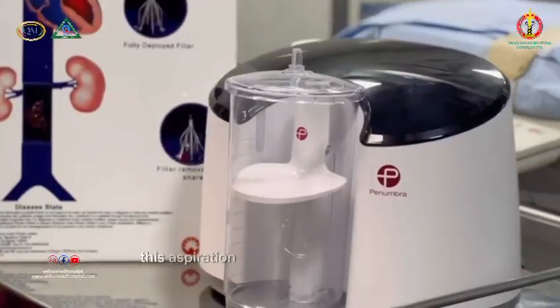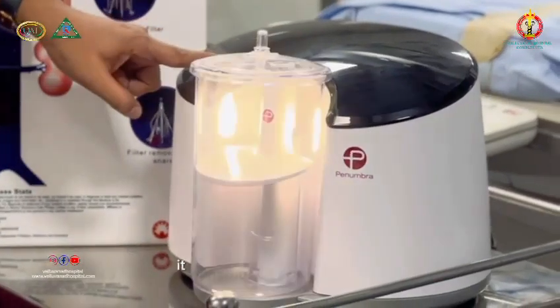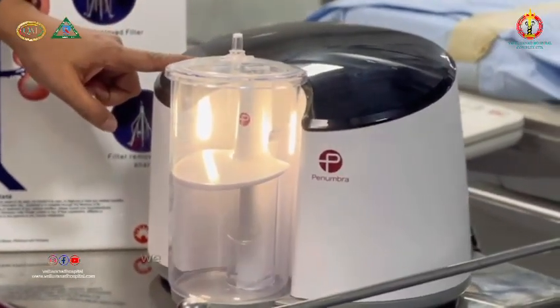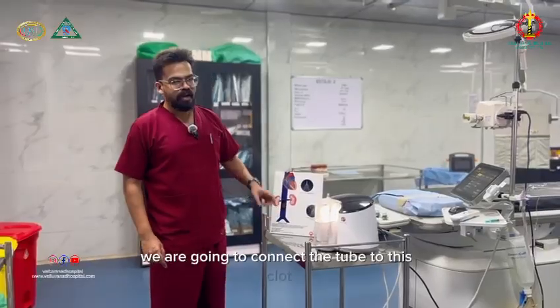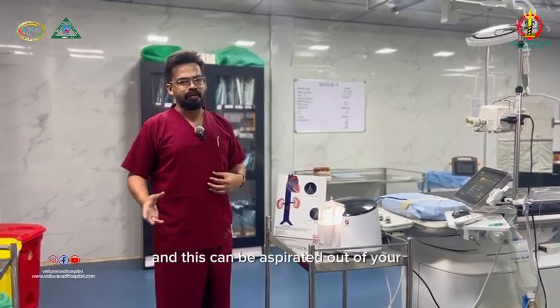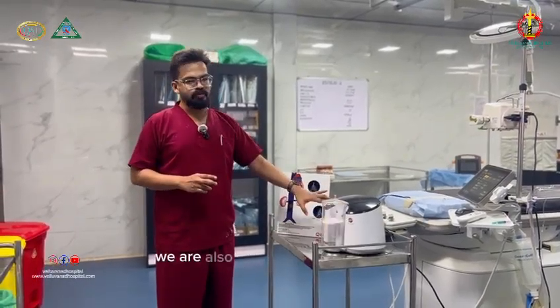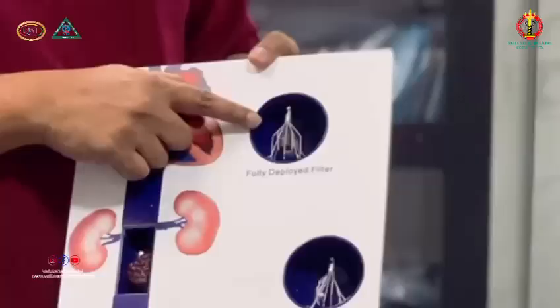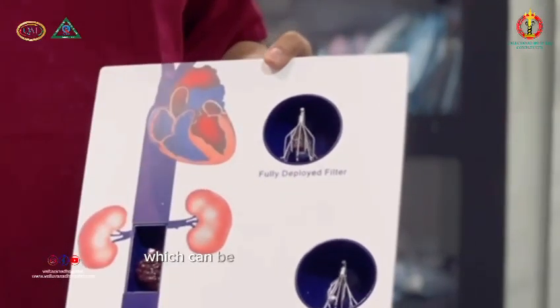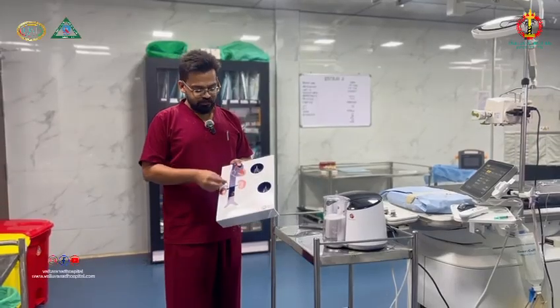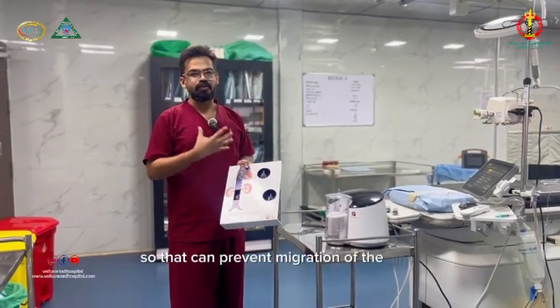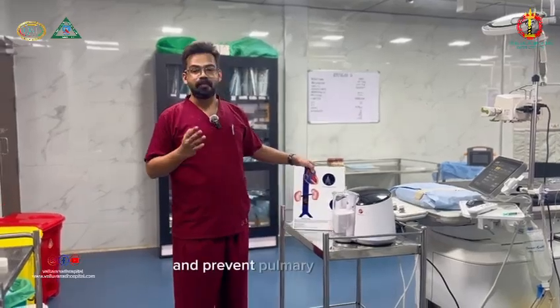When this aspiration pump is switched on, it generates negative pressure. Through this, we connect a tube to the clot, and it can be aspirated out of your body. In addition, we also use metallic filters, which can be placed above the level of the clot to prevent migration of the clot to your lungs and prevent pulmonary embolism.